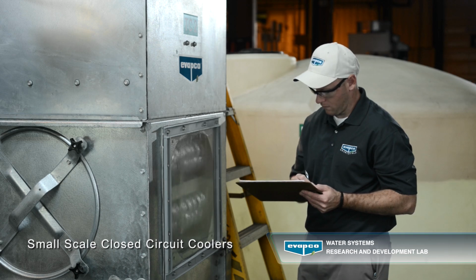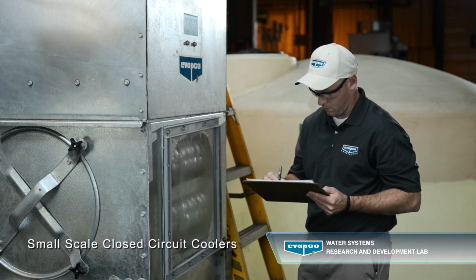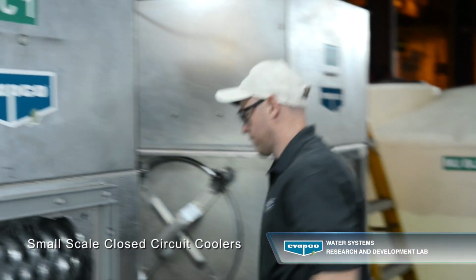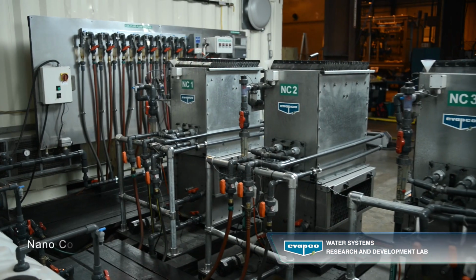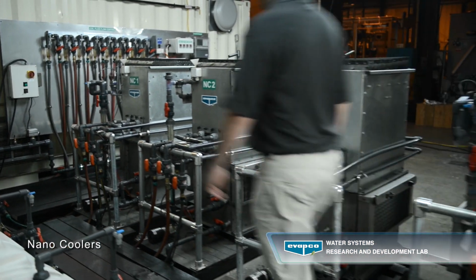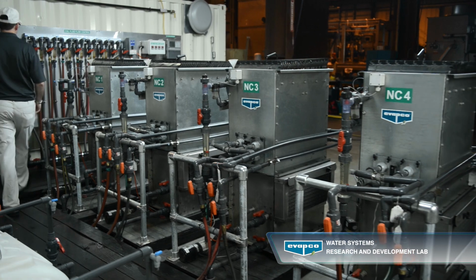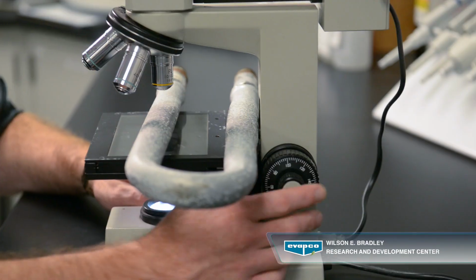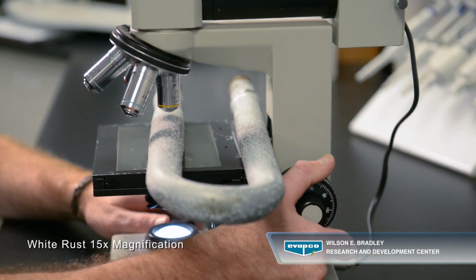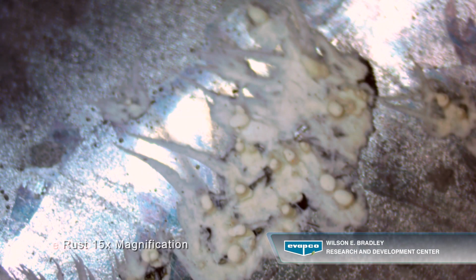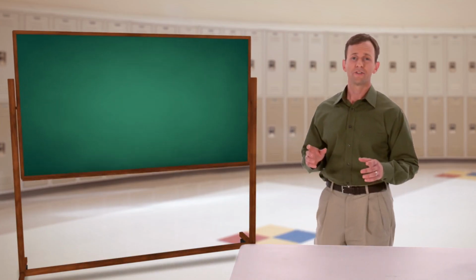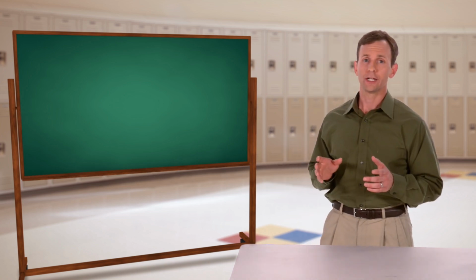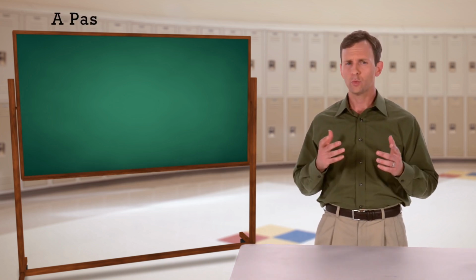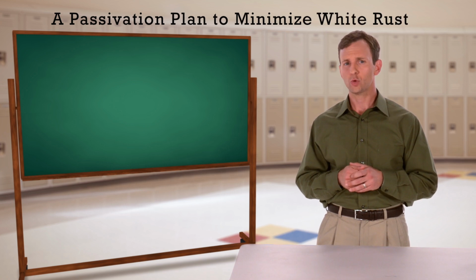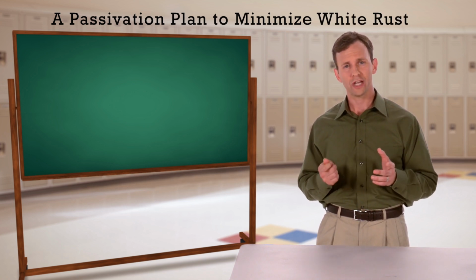This innovative test equipment provides the ability to study different methods of forming a stable passive layer to minimize white rust formation. But they didn't stop there. Evapco then built 4 even smaller nano coolers in order to accelerate the testing of commercially available products and increase the rate of new discoveries related to improving real-world passivation programs. The cause and effect of white rust has been well documented over the past 25 years. Even with this knowledge, new galvanized equipment continues to experience white rust damage.